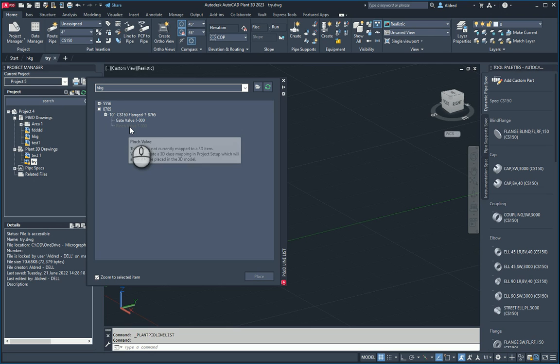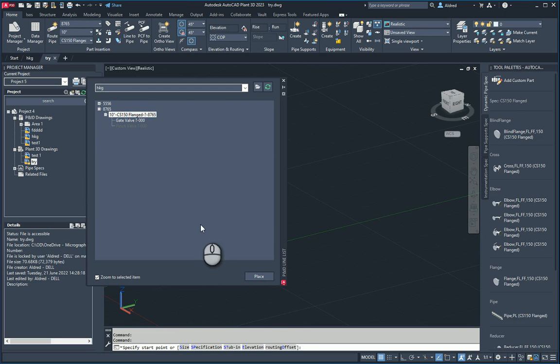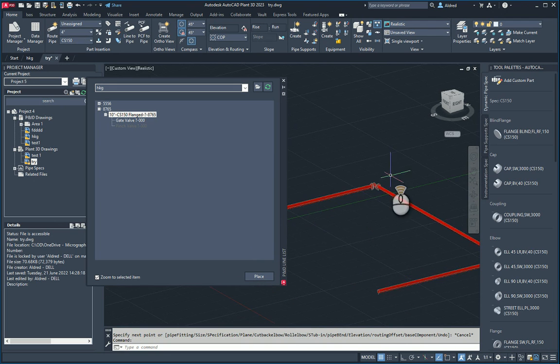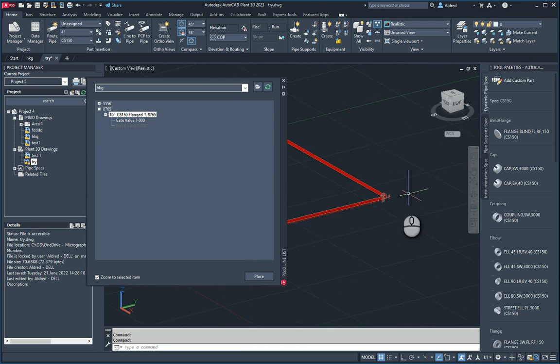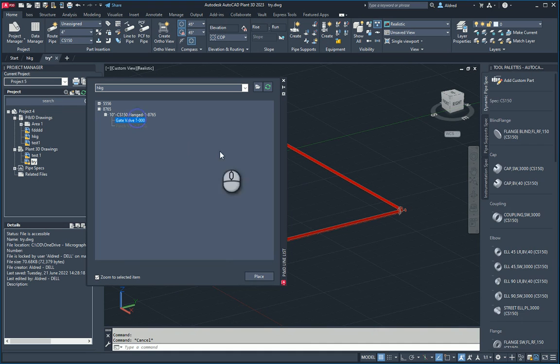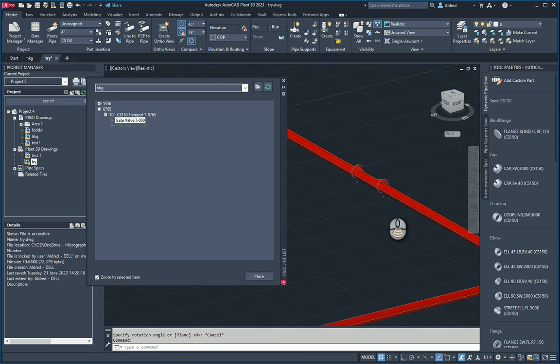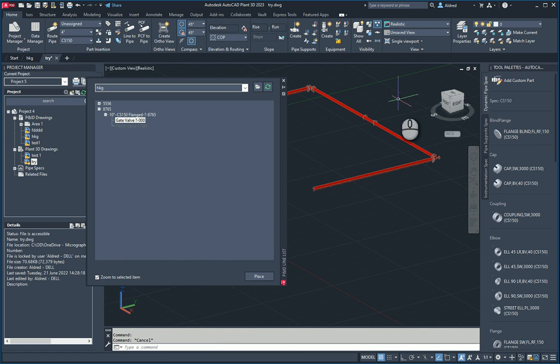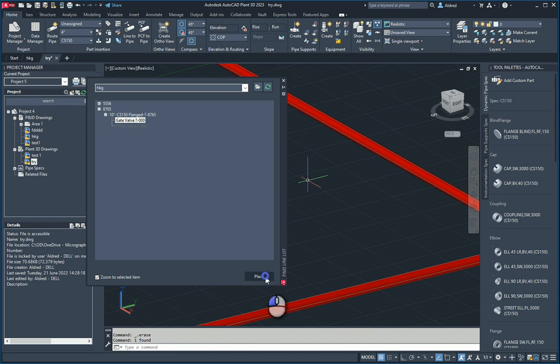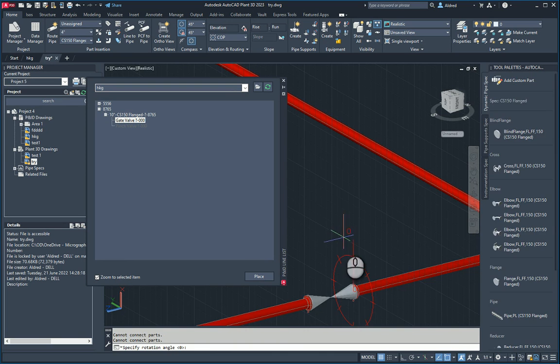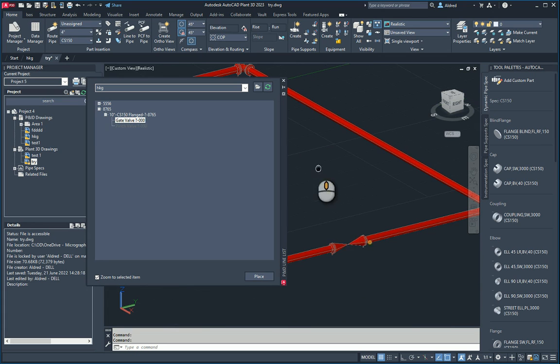I've got one gate valve. The pinch valve is not currently mapped to 3D items. So let's go to my flange, place it, and we should have a 10-inch pipe that I'm able to run — no errors. It's flanged as well. I'll put my valve in. This hasn't placed properly, but you get the point — it is mapped to the spec. I just didn't have my snap settings on, so this is another important reason why you should have your snap settings on.